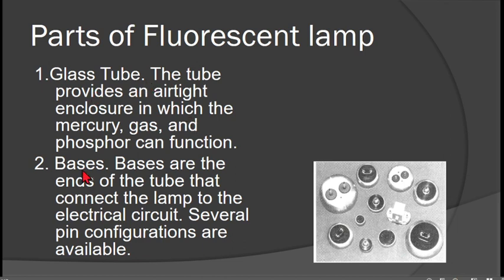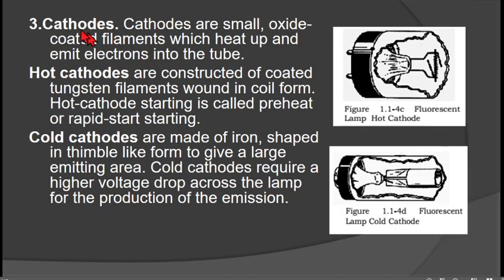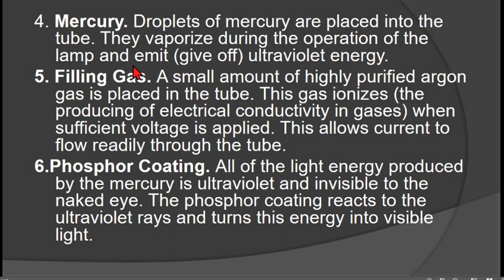The fluorescent lamp parts include the bases, the hot and cold cathodes, and mercury droplets. Mercury droplets are placed into the tube and vaporize during operation, emitting ultraviolet energy. A small amount of highly purified argon gas is also placed in the tube; this gas ionizes and produces electrical conductivity when sufficient voltage is applied, allowing current to flow readily through the tube. The phosphor coating then reacts to the ultraviolet rays and converts the energy into visible white light.